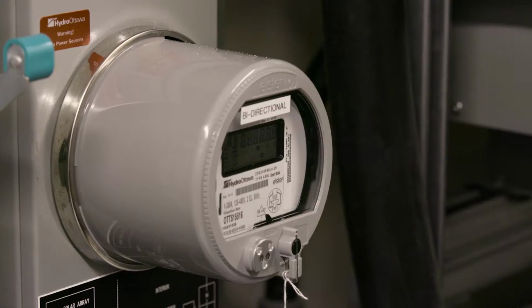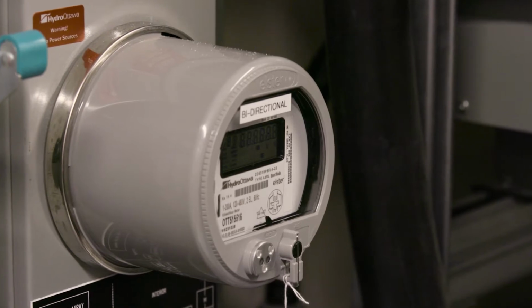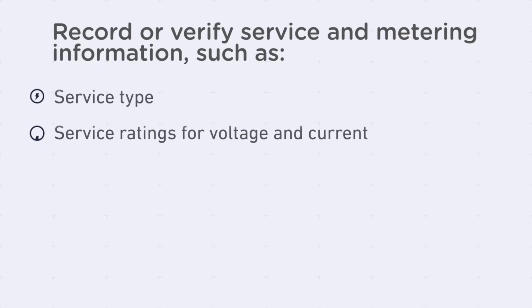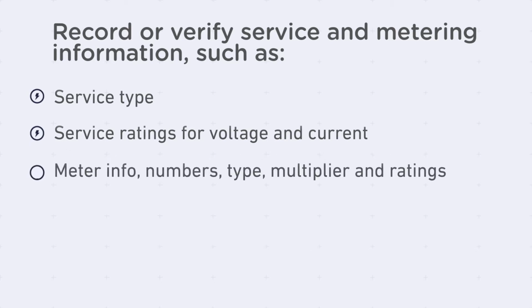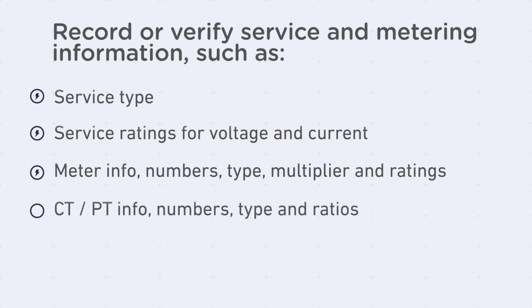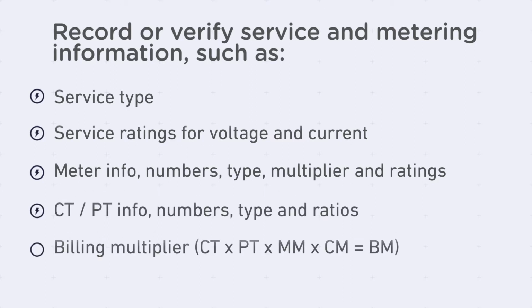C. Record or verify service and metering information such as service type, service ratings for voltage and current, meter info, numbers, type, multiplier, and ratings, CT/PT info, numbers, type, and ratios, billing multiplier. The billing multiplier is equal to CT ratio times PT ratio times meter multiplier times circuit multiplier. Next, identify the appropriate standard drawing.